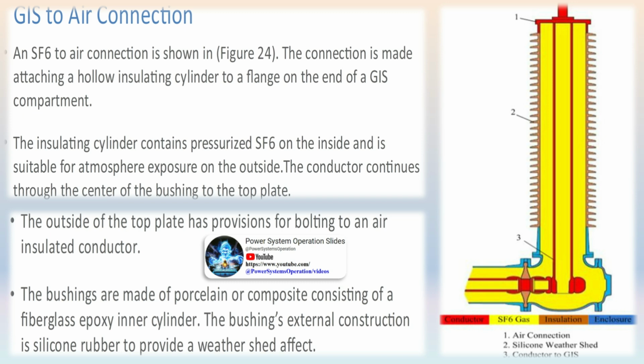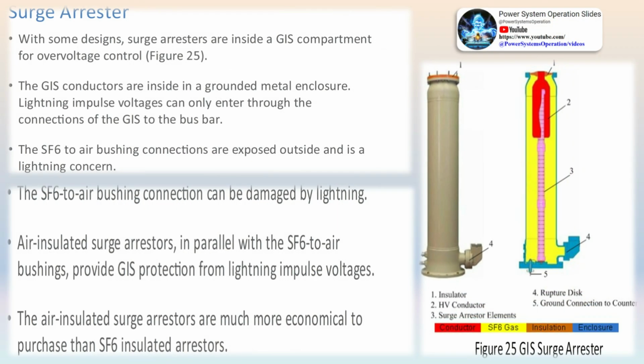Circuit breakers. Both AIS and GIS use basically the same type of dead tank SF6 puffer circuit breaker. However, with GIS systems, instead of SF6 air bushings mounted on the circuit breaker enclosure, the GIS circuit breaker is directly connected to the adjacent GIS module.